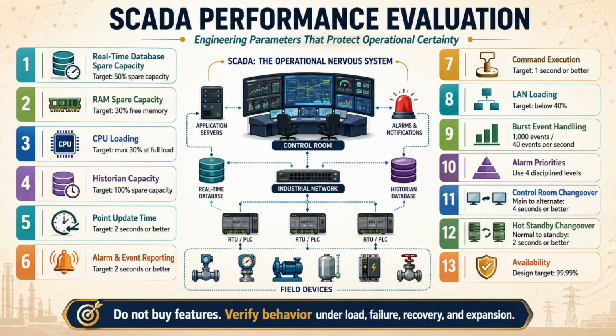The 10th engineering parameter is alarm and event reporting time, because a late alarm can be worse than no alarm when it creates false confidence. The operator believes the system is quiet while the process has already moved. So alarm reporting must be tested from field detection through controller or RTU timestamping, communication transport, SCADA acquisition, alarm evaluation, display update, annunciation, and event logging.